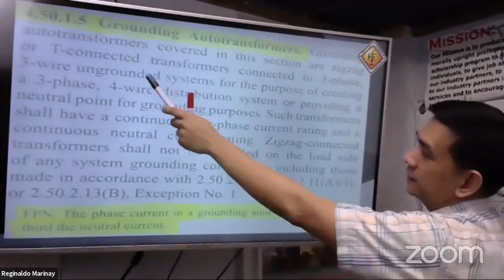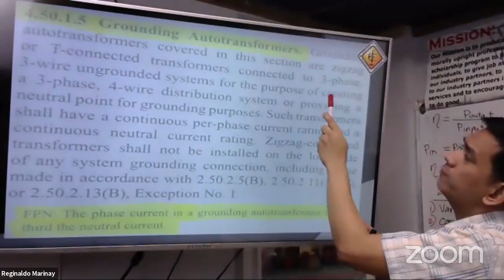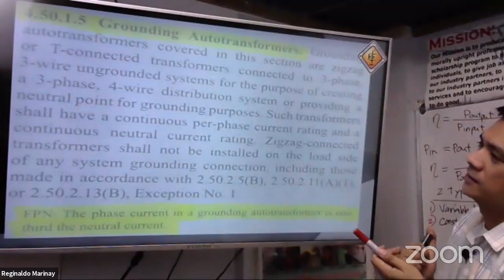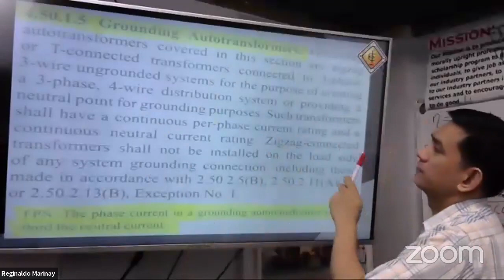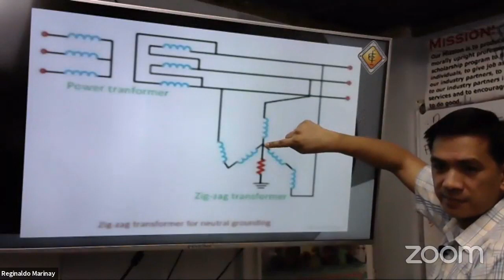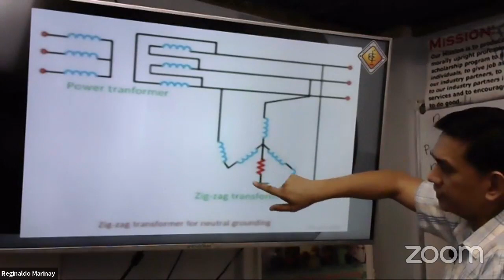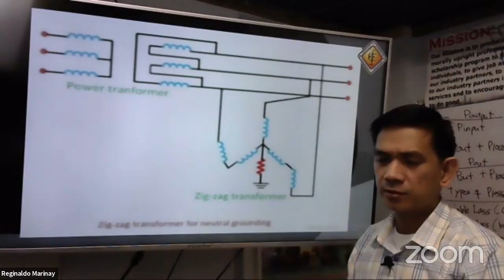Now, the T-connected transformer connected to a 3-phase, 3-wire ungrounded system for the purpose of creating. You see, take a look at the purpose. What is the purpose? For the purpose of creating the 3-phase, 4-wire distribution system. You see, this will create a 3-phase, 4-wire or providing a neutral point for grounding purposes. There is a neutral point here. You see? For grounding purposes. And the primary objective or purpose of grounding is for safety. Isn't it?